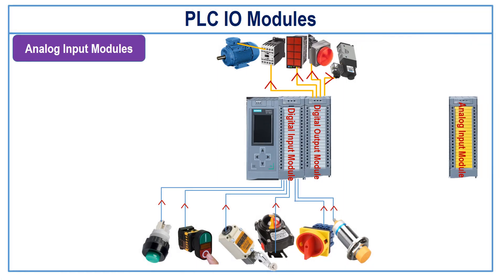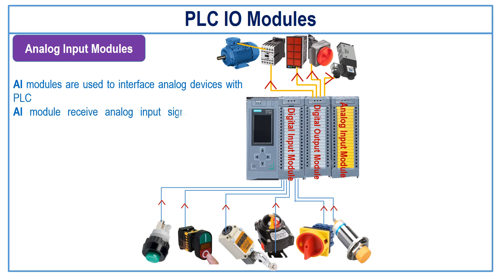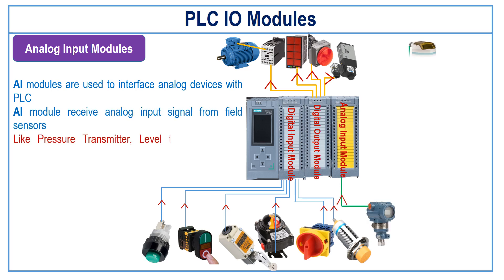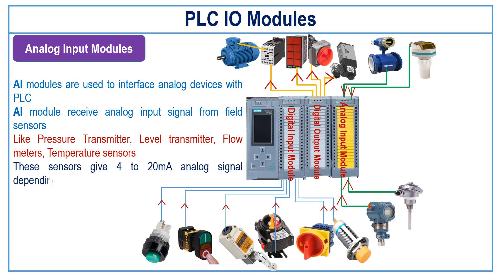Analog input modules: The analog input modules are used to interface the analog devices with the PLC. Analog input modules receive the analog input signal from field sensors like pressure transmitter, level transmitter, flow meter, or temperature transmitter. These devices give a 4 to 20 mA or 0 to 5 V analog signal depending on the process value.